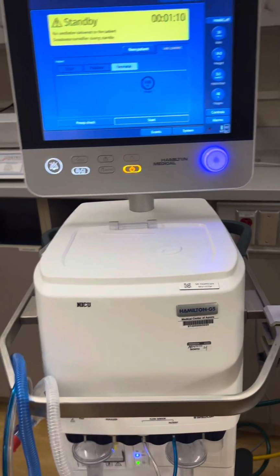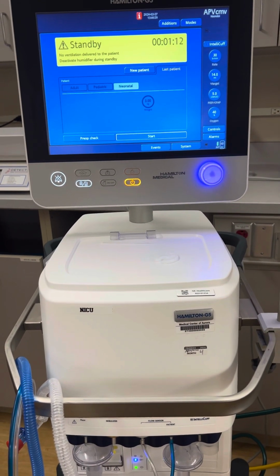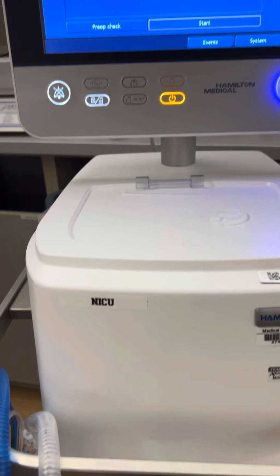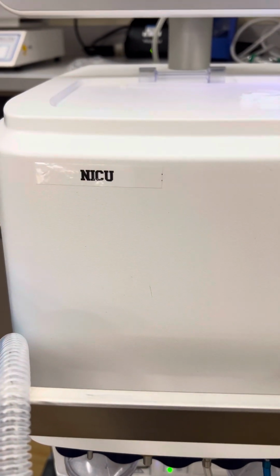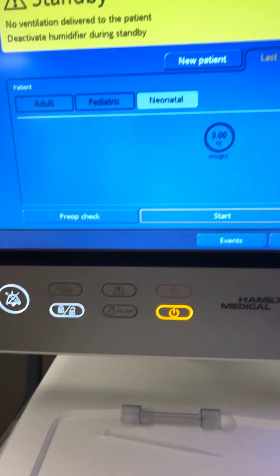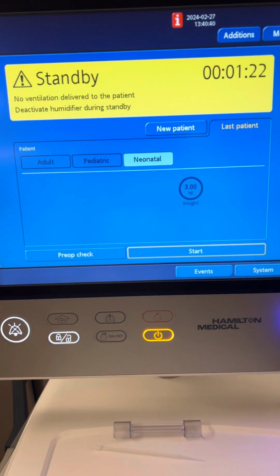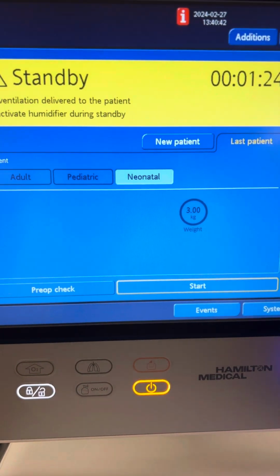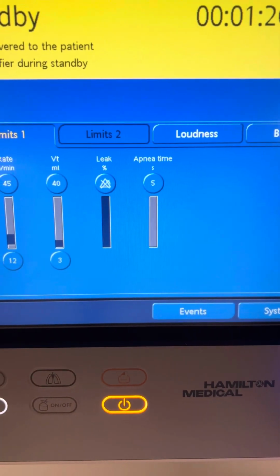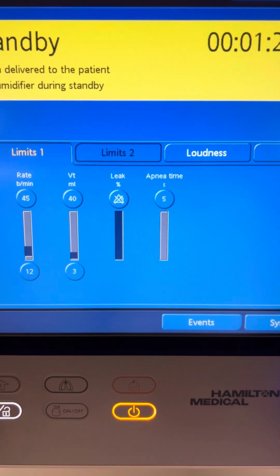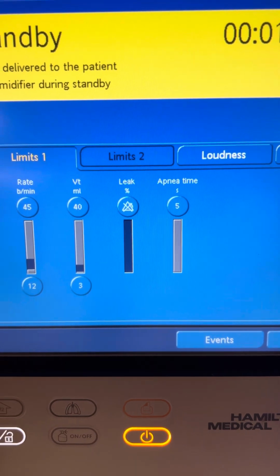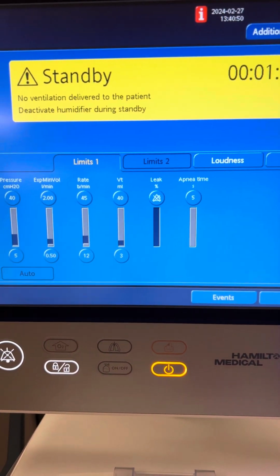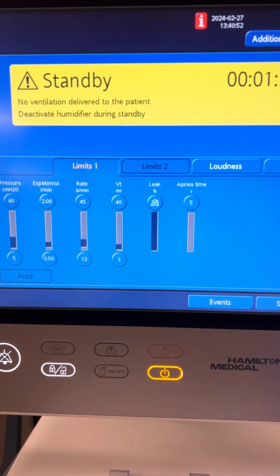I just want to briefly run through the G5 ventilator in the neonatal setting. The two that I have over here will be labeled NICU. You can pull the other vents at any time; you would just have to change some of the settings. So these ones have been configured to default to the neonatal population. And then we also have leak percentage that we can monitor, based on what the baby's leak is.